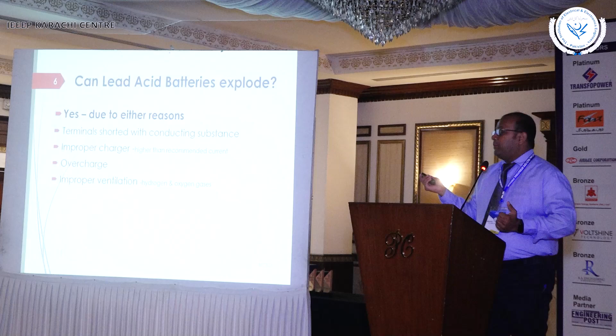Improper ventilation is also a reason because this battery is composed of chemicals in it. So ventilation of air is important so that the battery will not heat up so much. The last thing regarding this problem is the vent holes. Normally on all liquid batteries, we have vent holes, which are normally yellow in color. On that vent hole there is a small hole from which ventilation takes place. It is not a common practice to clean these holes, but that is the reason this battery may explode because of non-ventilation. The gases cannot come out from the chambers and it may cause an explosion.